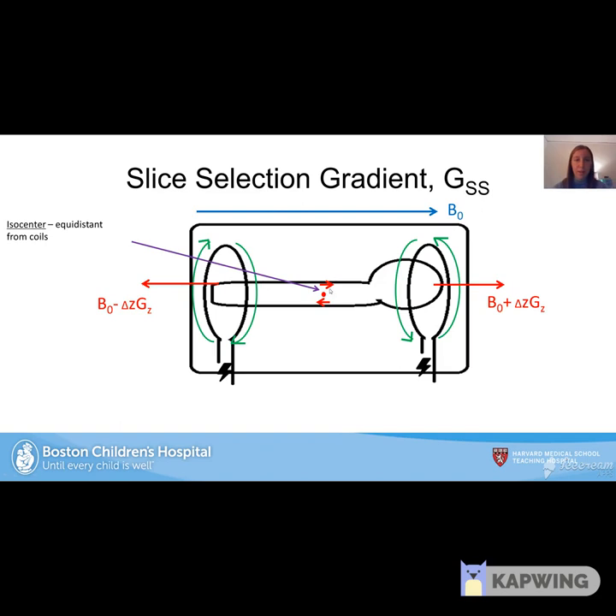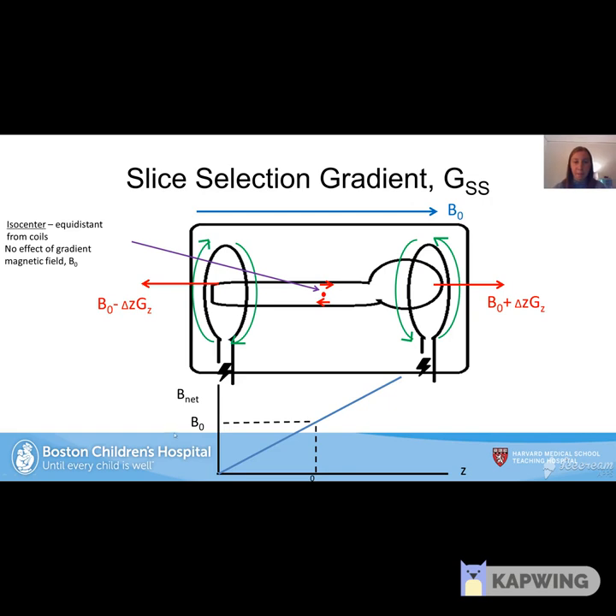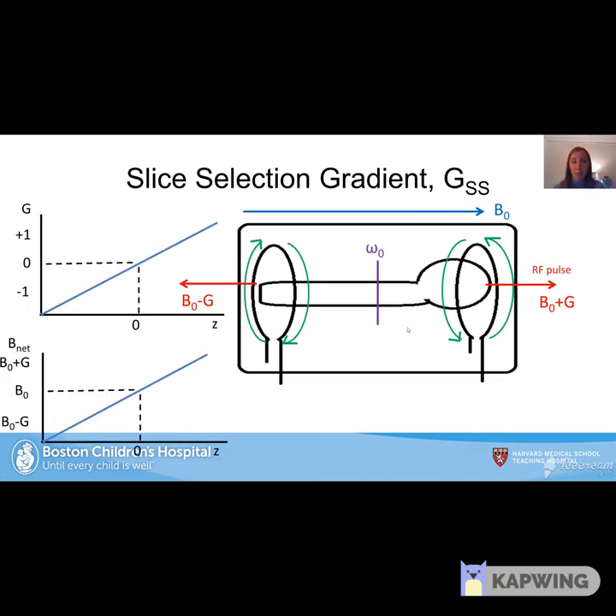At a point equidistant between the two gradient coils — the isocenter — there is no gradient effect, so protons see only B-naught and precess at omega-naught. B-naught as a function of z changes linearly. Protons at positions away from isocenter see different field strengths and precess at different frequencies. We can select a slice by sending an RF pulse at omega-naught and receiving signal at omega-naught. The receiver coil receives signals at different frequencies, enabling selection of different slice locations.